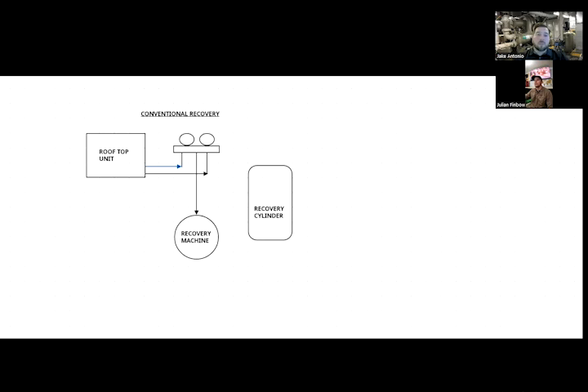So what you're going to be doing is pulling the refrigerant from both sides of the system into your manifold set. And then on your charging hose, you're going to go through your recovery machine. Most smaller recovery machines can handle vapor and liquid. It depends on the brand. So just make sure you understand what kind of recovery machine you have.